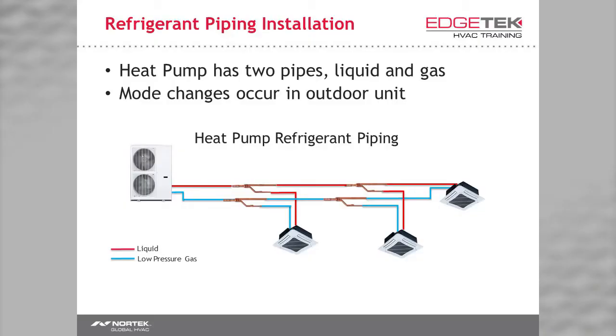At its most basic, a mini VRF piping system has a lot of similarities with a traditional split heat pump system. You have one liquid pipe and one gas pipe, colloquially known as suction pipe, in a 1-to-1 combination, where you have one outdoor unit and one indoor unit. It is exactly the same as a regular heat pump.